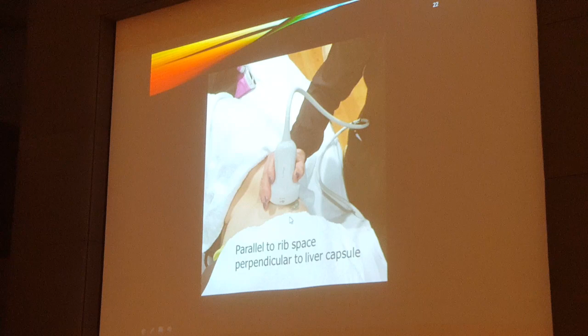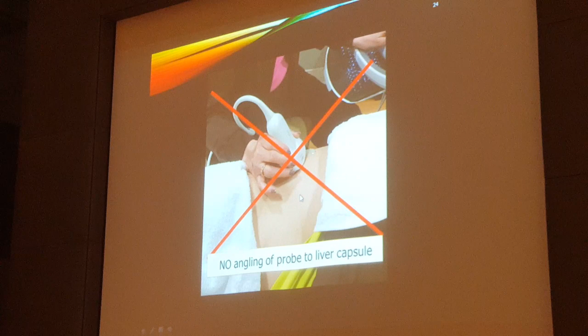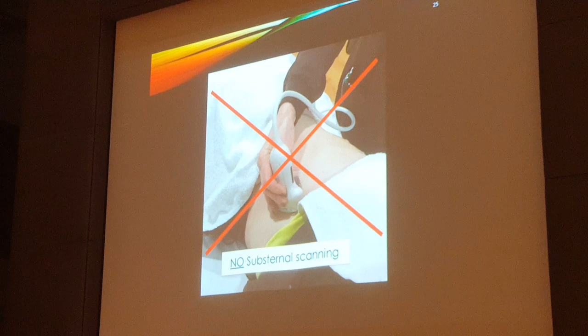So again, what we want to do is place the transducer parallel to the rib space and perpendicular to the liver capsule. You do not want to place the transducer across the ribs. You don't want to angle the probe to the liver capsule. You don't want to use substernal scanning, and no angling to evaluate the left lobe of the liver. You also don't want to put the ROI box very deep, because again, the RF pulse is attenuated as it goes through the liver, and therefore it's weaker as you go down in the liver. So the ideal position is about 4.5 centimeters from the transducer, but still maintaining 1.5 centimeters from the liver capsule.